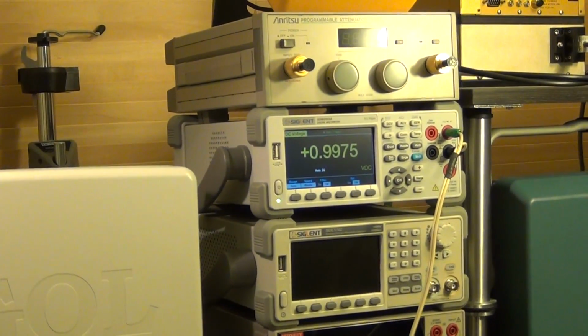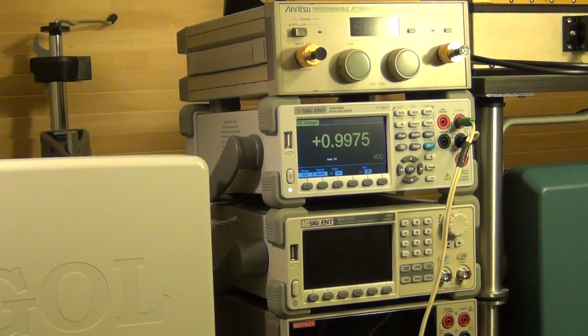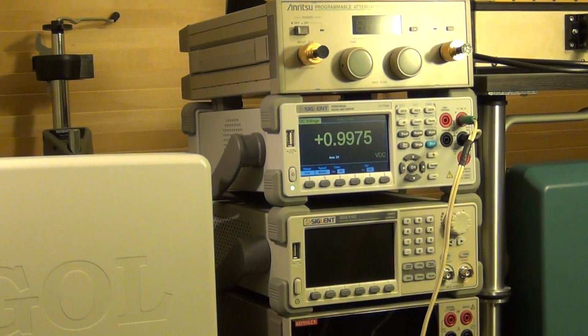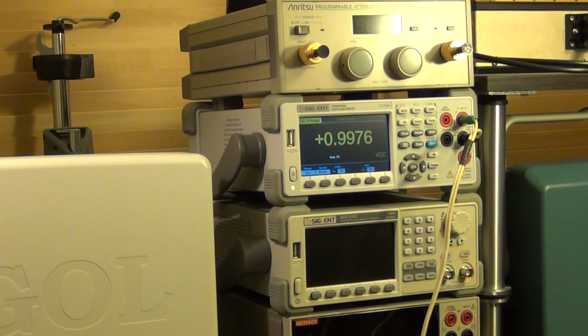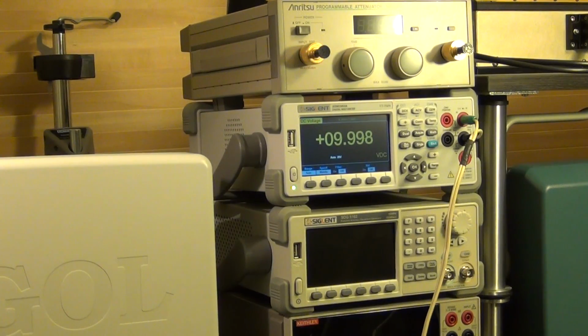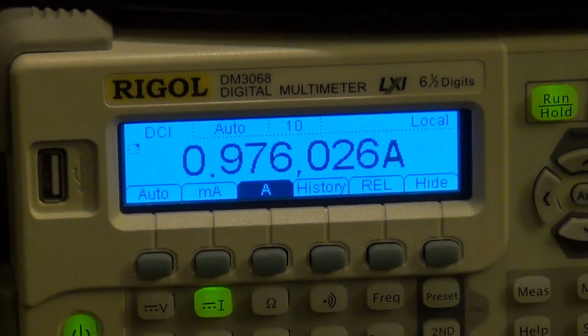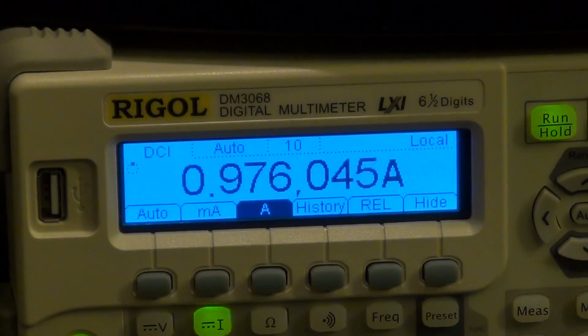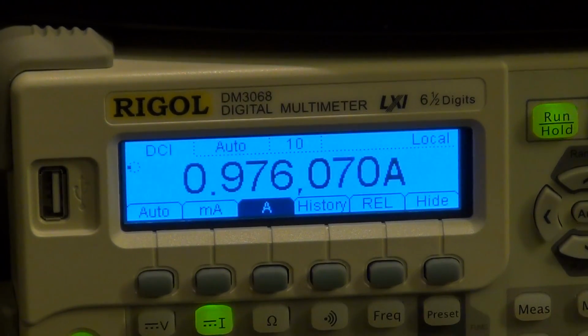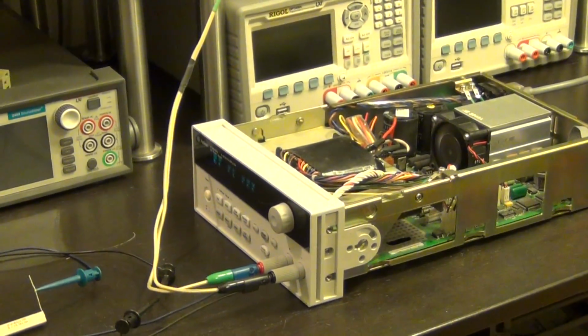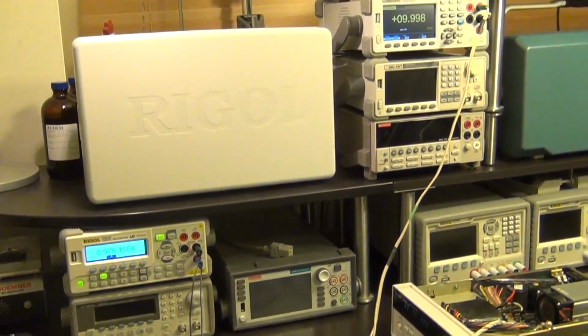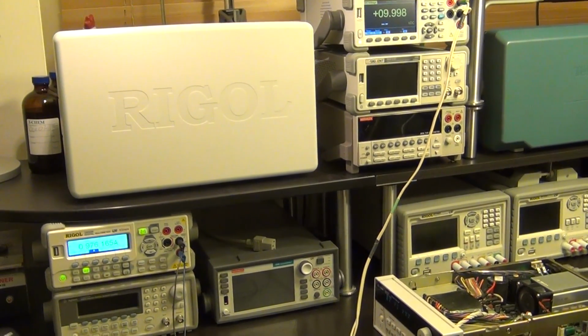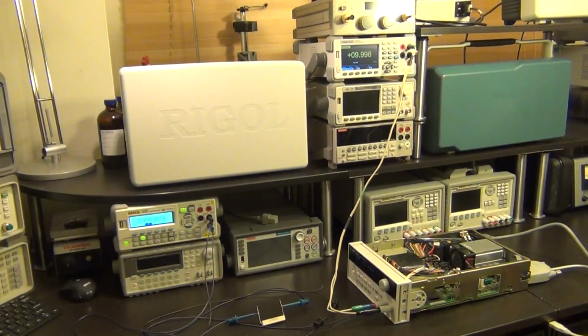So let me set it to a different voltage. Let me set it to 10 volts. I change the range so we can make sure the range works. I'm setting it to 10 volts, and there we go, 9.998. You can see the fan just kicked up because it's consuming a lot more current, and this should say about 1 amp, and it does, and you can see that it's slowly rising as the resistor is changing temperature. So it looks good. I can't believe it. So the supply is actually working, even though the display is still showing that gibberish. That is a huge discovery. So communicating through the computer through the GPIB paid off. It allowed us to debug it.